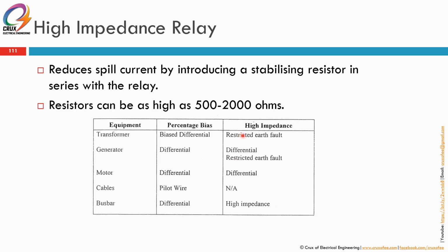So types of differential relay, kita ada yang jenis high impedance. So dia reduce spill current by introducing a stabilizing resistor lah. Tadi restraint coil punya differential relay. So this one is a high impedance. They introduce a stabilizing resistor in series with the relay. So the resistor can be as high as 500 to 2000 ohms lah. So depends on the type of relay lah.